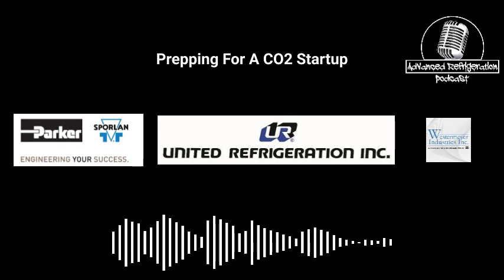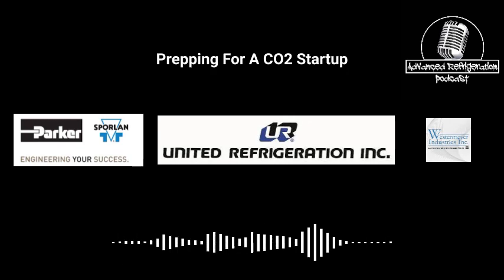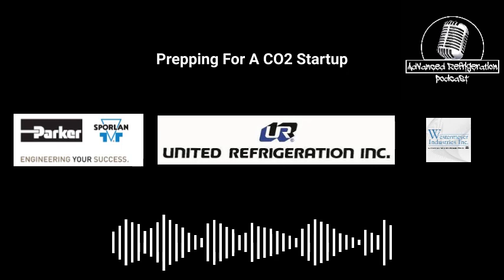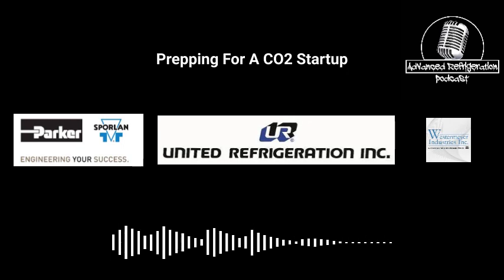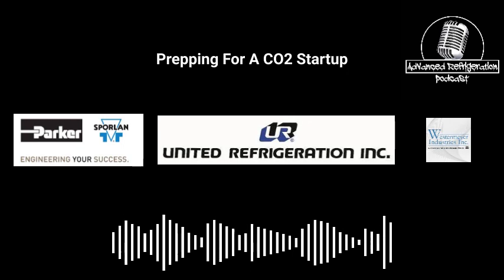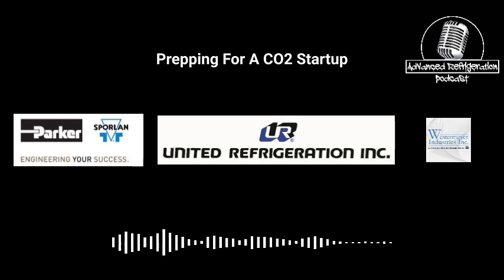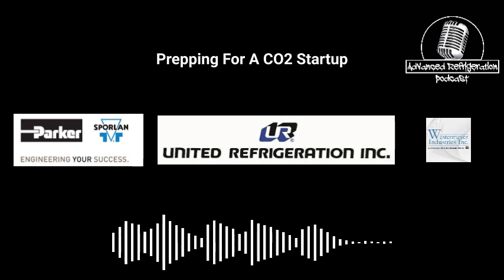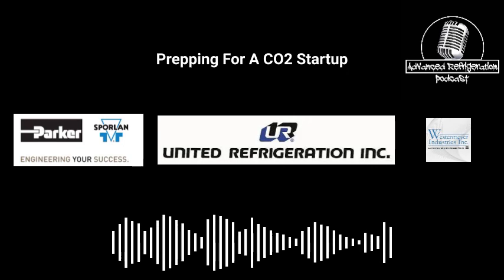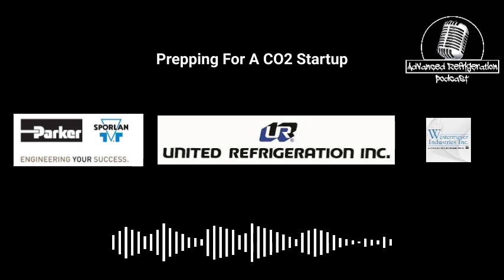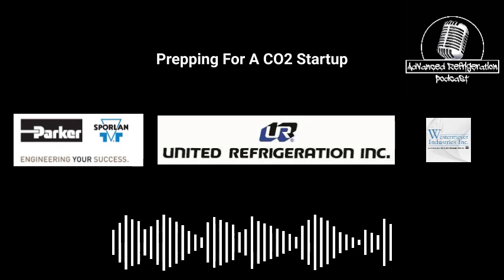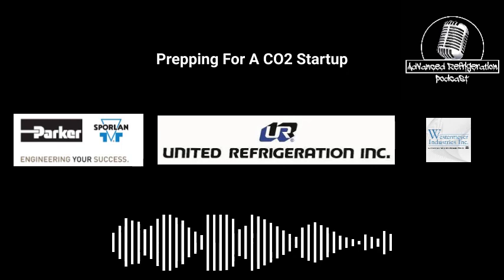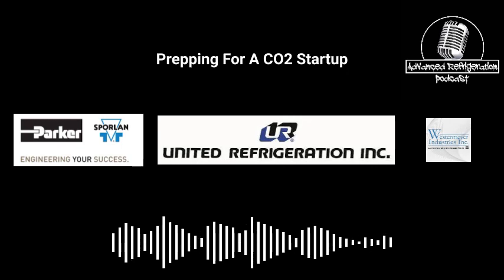So what Kevin's saying is, if you go in there and go to Menu 5, Configured Applications, go to whatever case controller you're talking about, whether it be the S3C, the Core Link, the XM, or the CC200, and hold down the Control button and hit Page Down while you're reading the transducers, it'll skip through every single case, so you can see what each case is actually running. Theoretically, if you're pressurizing the system to the same pressure all the way around, every single pressure transducer should read the same pressure.